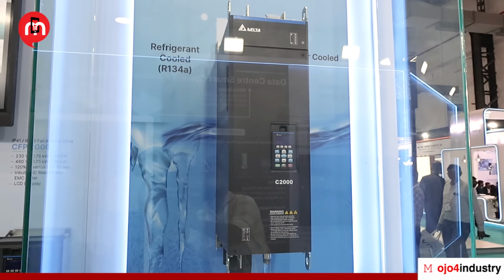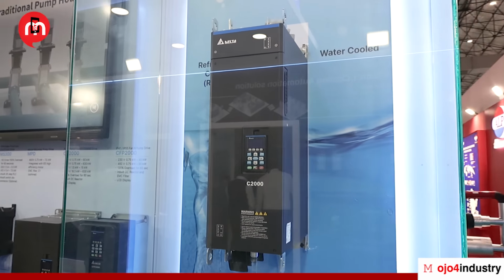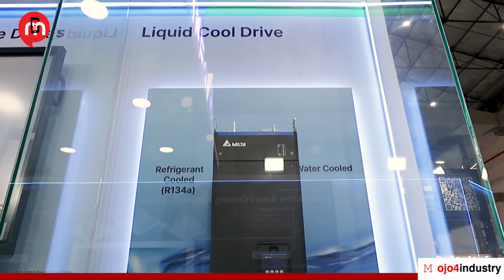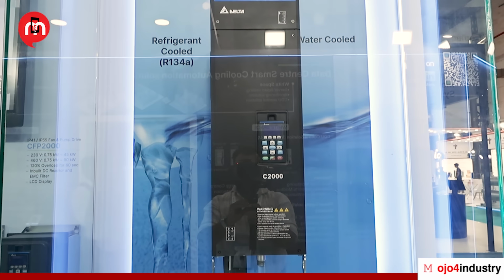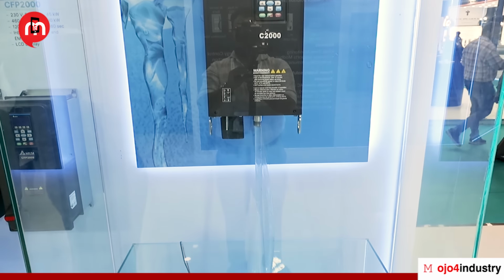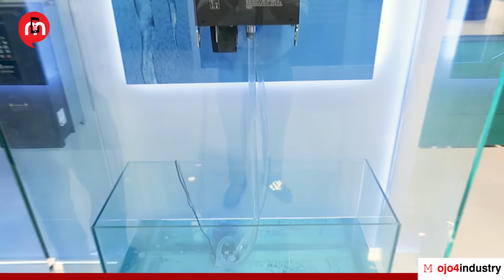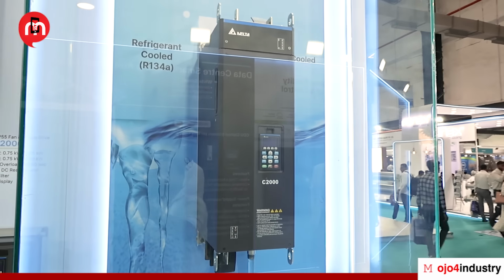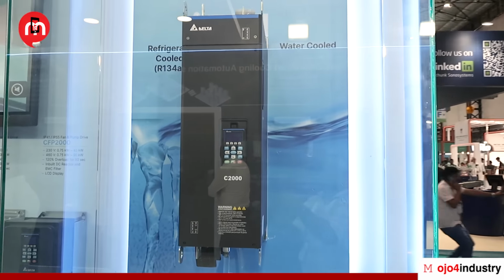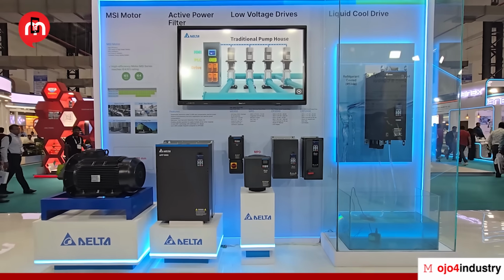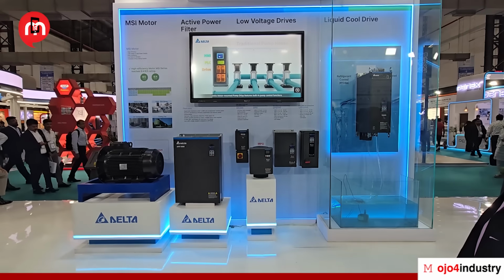We also displayed the liquid cool drive. An air cool drive requires a big panel and proper ventilation for the cooling to happen. But with the liquid cool drive, it can be water or glycol based, or any refrigerant into the drive. The efficiency is high, and you don't need a cabinet - it's already an enclosed IP66 cabinet.